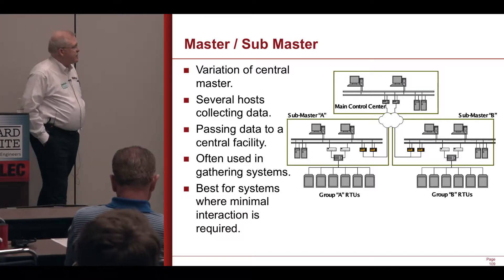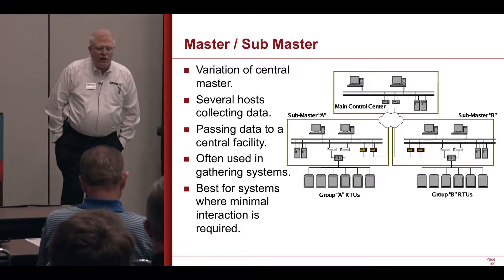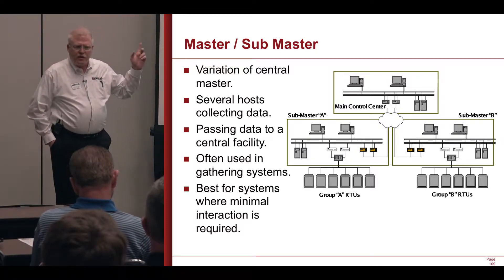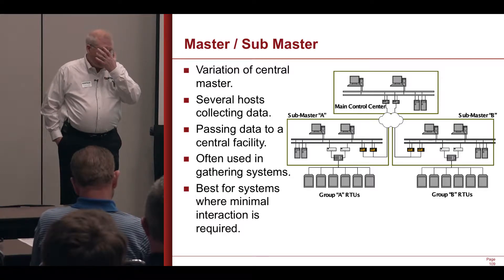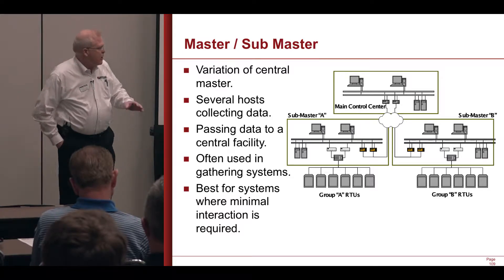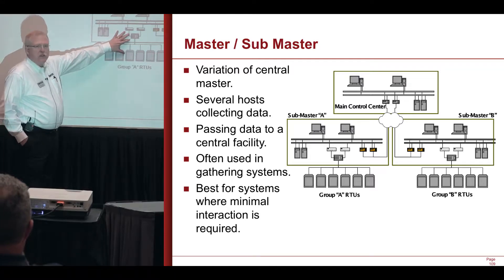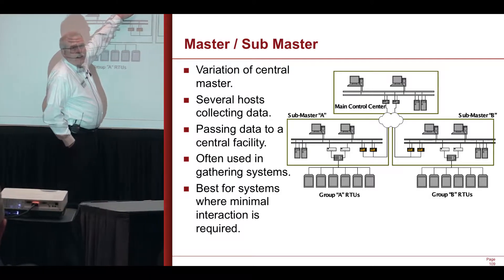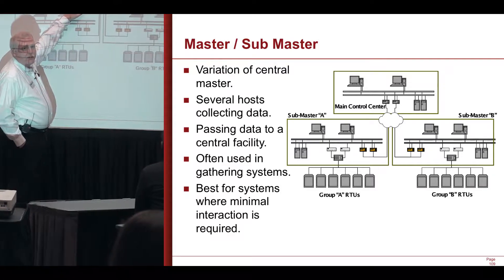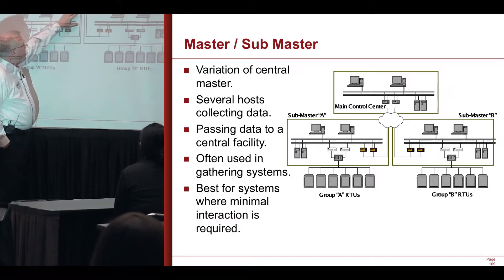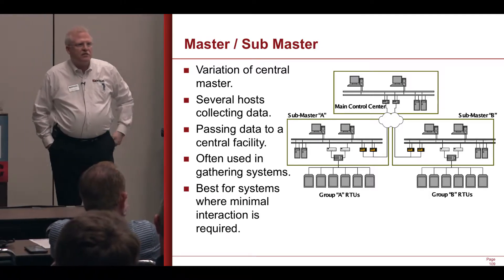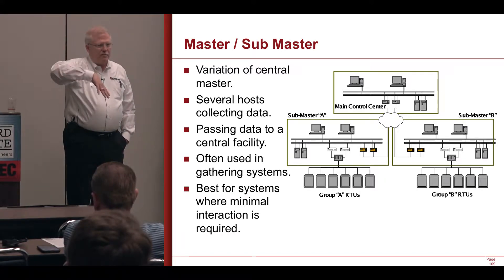The next kind of SCADA system is what I would call a master-submaster. You don't tend to see these in the U.S. very much. They're fairly common internationally where you have big state-owned companies — for example, this would be the control system for a gas utility, a set of city gates around a community, and this would be the interstate transmission pipeline control system, and it's polling these guys. Rather than polling the devices directly, it's polling the servers that are polling the devices. So I'm rolling it up — it's a master-submaster.